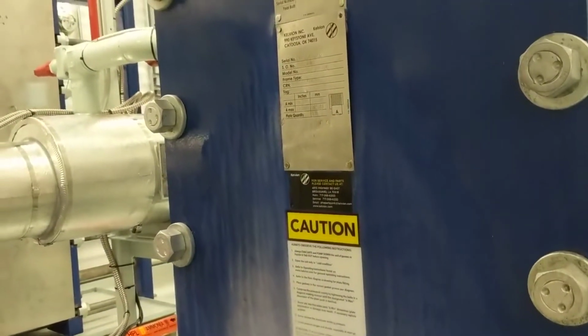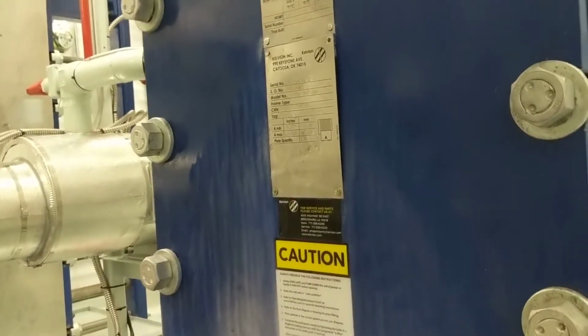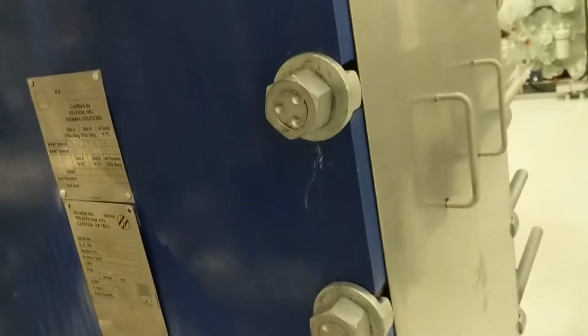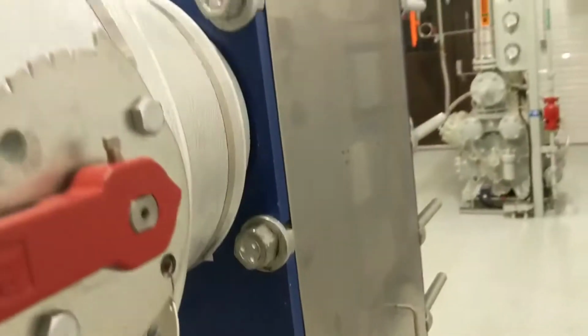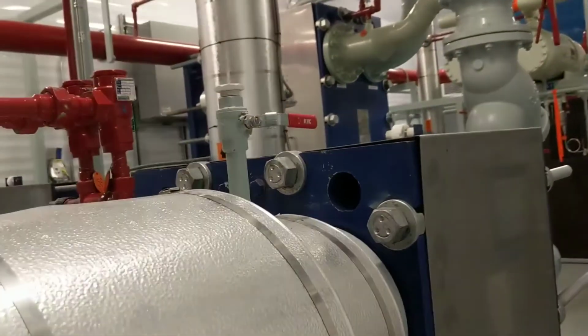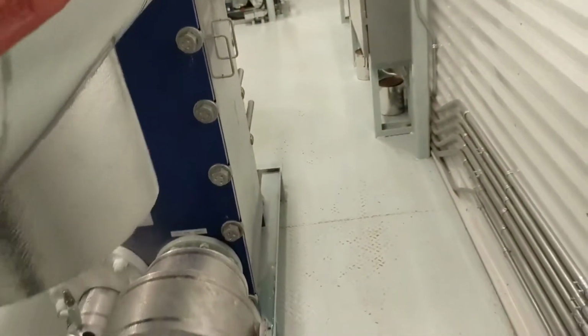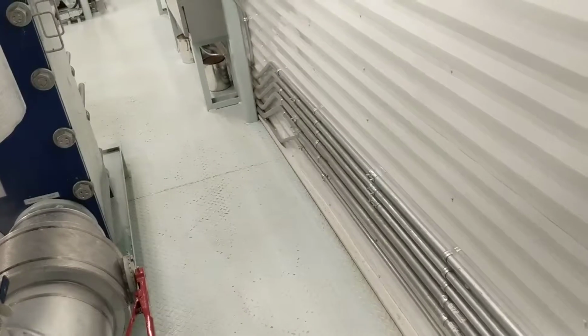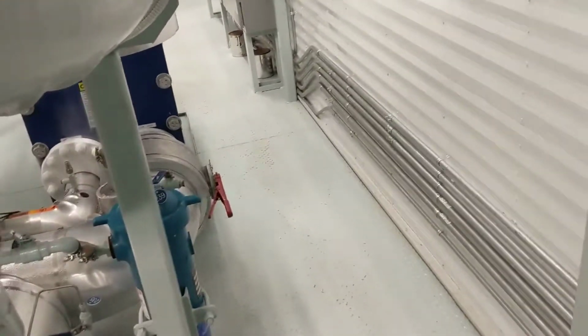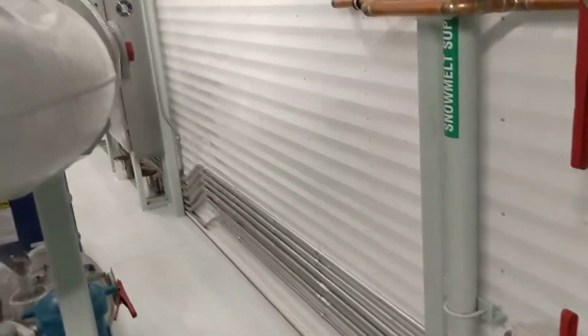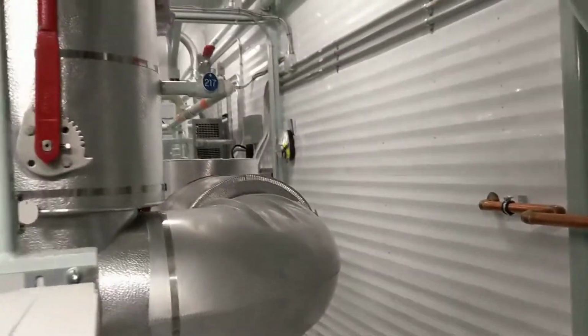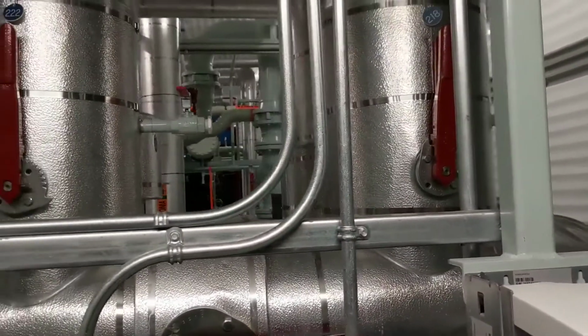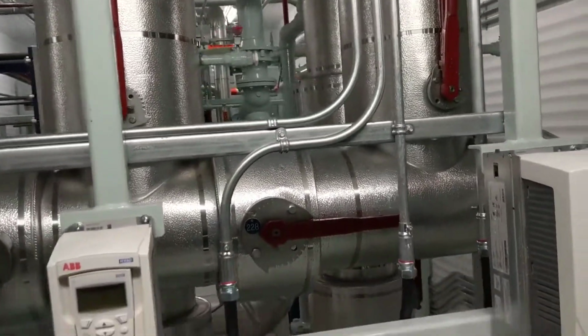As the ammonia is boiled off by the low pressure state that's created by the compressors when they apply suction to it, it's taking the heat from the brine and transferring that heat into the ammonia. In the video on ammonia, I covered how that heat is moved through the compressors and gives up its heat to the glycol in the condenser.